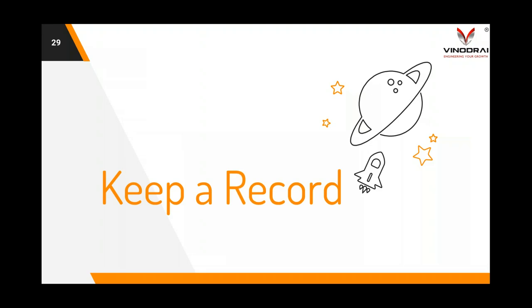So I would like to leave you with one thing: always maintain a record. Maintaining once or twice or regularly is not enough, but keep a record of what you have maintained. For example, in a gas burner, we needed to check the pressure of the first stage regulator and the pressure of the second stage regulator. So you need to keep a record of all of this: I checked 1 month before, the pressure was this; the second week the pressure is this; the third week the pressure is this.